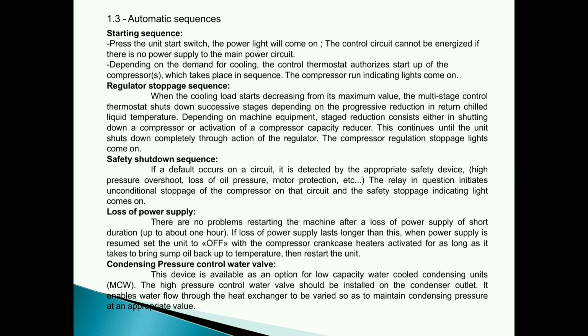Regulator stoppage sequence. When the cooling load starts decreasing from its maximum value, the multi-stage control thermostat shuts down successive stages depending on the progressive reduction in return chilled liquid temperature. Depending on machine equipment, staged reduction consists either in shutting down a compressor or activation of a compressor capacity reducer. This continues until the unit shuts down completely through action of the regulator. The compressor regulation stoppage lights come on.